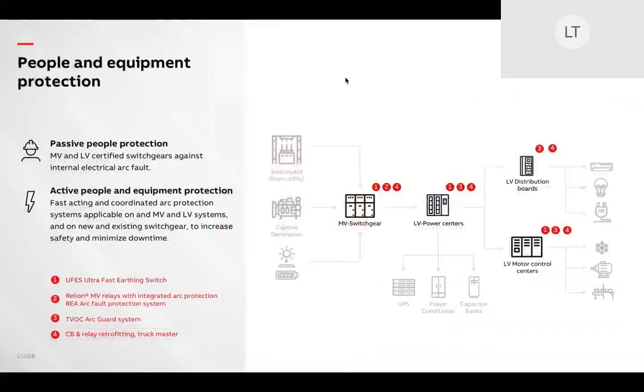So how can we protect people and equipment? Well, we can help in two ways. The first is through passive protection in the form of switchgear that is designed and certified against internal arc faults. For example, our medium voltage switchgear IEC solution UniGear with an internal arc withstand current of 50 kA, providing full AFLR protection to the operators. So that is all around front, lateral and rear. That gives safety to the operator when they're stood around the switchgear.